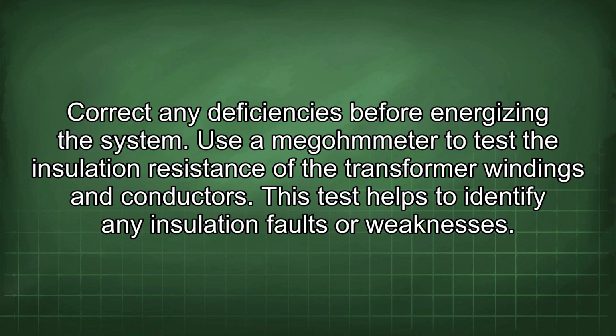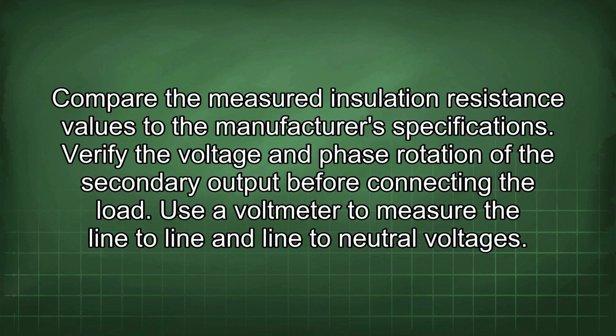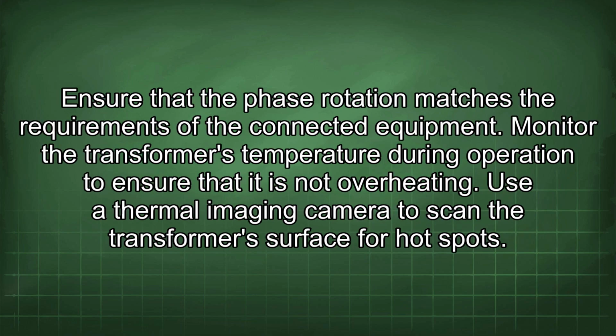Use a megohmmeter to test the insulation resistance of the transformer windings and conductors. This test helps to identify any insulation faults or weaknesses. Compare the measured insulation resistance values to the manufacturer's specifications. Verify the voltage and phase rotation of the secondary output before connecting the load. Use a voltmeter to measure the line-to-line and line-to-neutral voltages. Ensure that the phase rotation matches the requirements of the connected equipment.